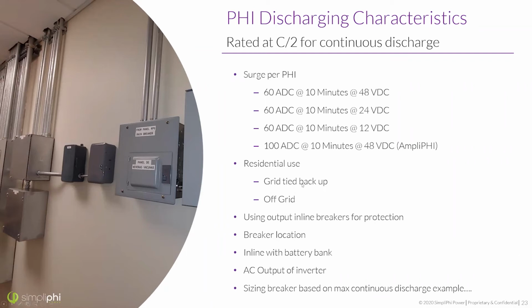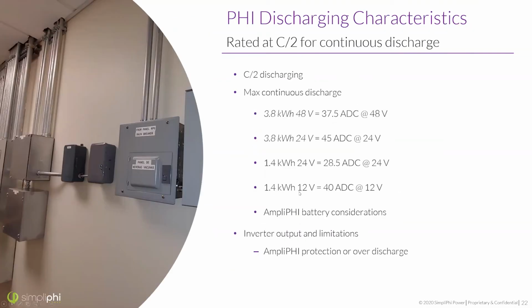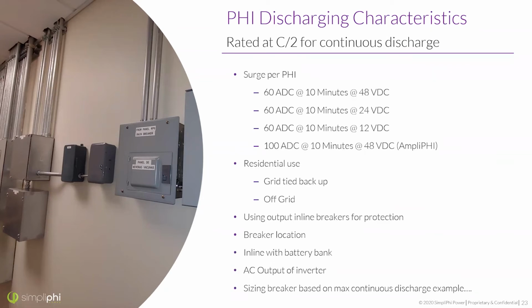Now, as far as C/2 goes and residential use, keep in mind that you really aren't going to be using the limit. These limits are rarely going to be touched if you're sizing correctly for most use cases. Most people don't come to you with an off-grid system and say, hey, I want 2 hours of battery life, so you really should be sizing larger either way. Grid tied, maybe you might have a customer ask you for a 2-hour discharge battery, but most of the time they're going to be wanting more time of discharge than C/2. So those limits shouldn't really be a problem in a real world application if you are sizing correctly.